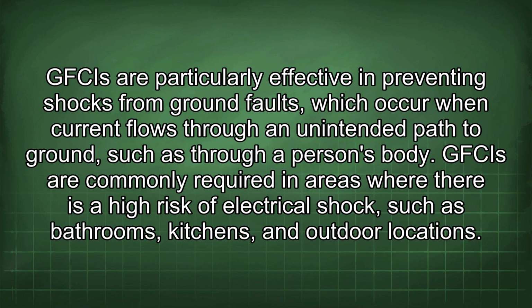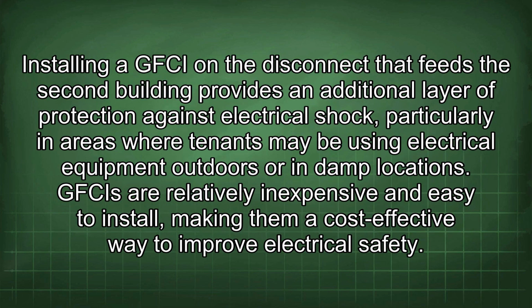GFCIs are commonly required in areas where there is a high risk of electrical shock, such as bathrooms, kitchens, and outdoor locations. Installing a GFCI on the disconnect that feeds the second building provides an additional layer of protection against electrical shock, particularly in areas where tenants may be using electrical equipment outdoors or in damp locations. GFCIs are relatively inexpensive and easy to install, making them a cost-effective way to improve electrical safety.